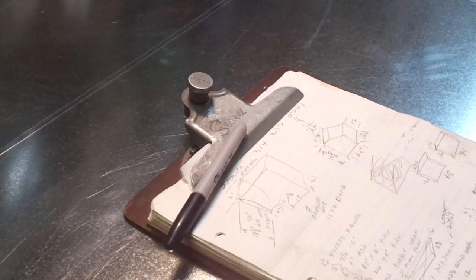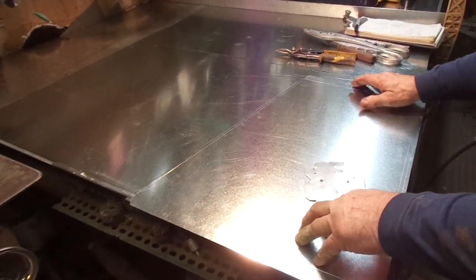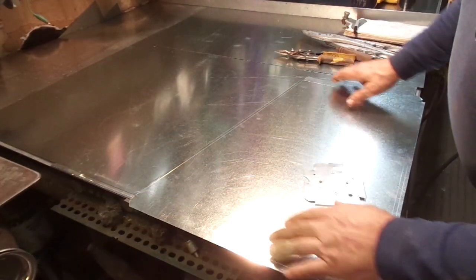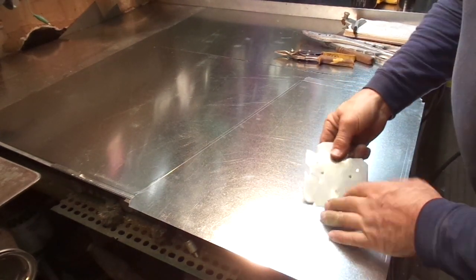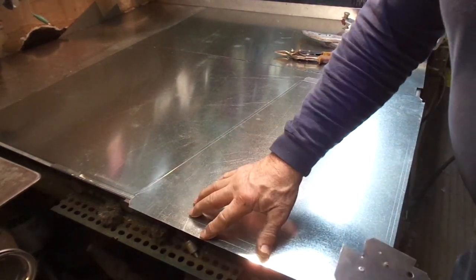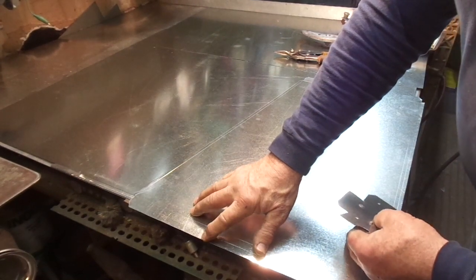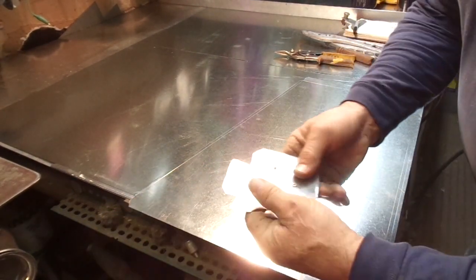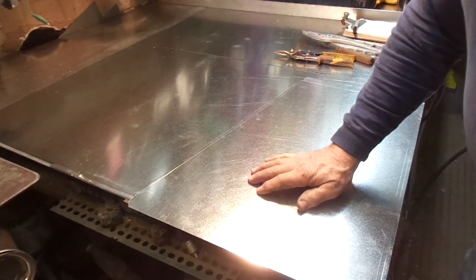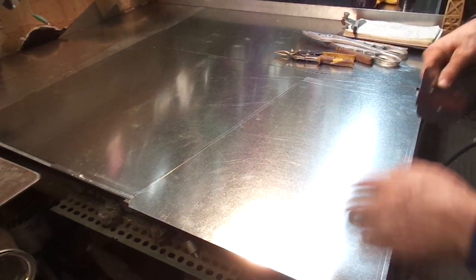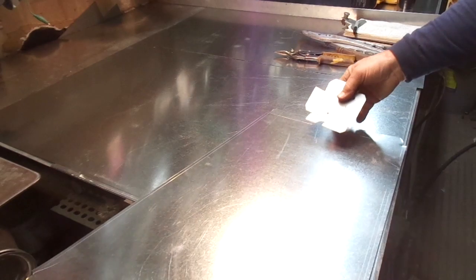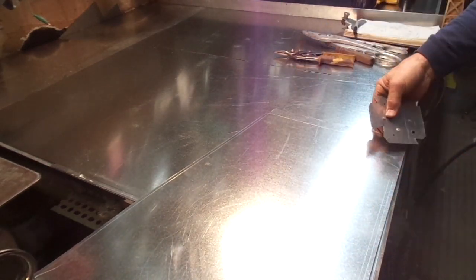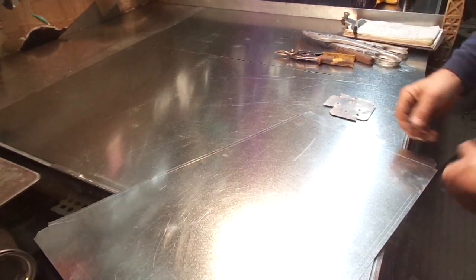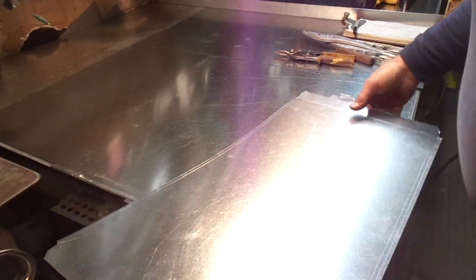Those are the things you can do to kind of streamline your layouts, or the thoughts in your layouts while you're measuring up a job. First thing you do, you figure out what the cut size is going to be, allowing for all your flanges and everything like that. Lay out your cut size, then take your scribe, and you know we're going to have a half inch 90 degree double hem flange, so you can mark an inch, turn your scribe over, grab the half inch and mark the half inch, mark your quarter to the full length, and then you go to the other end and you mark your 1 inch, which is going to be the notch for the half inch drive tab that folds over from the outside.